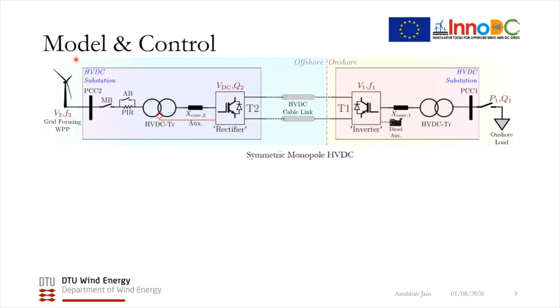The offshore wind power plant operates in grid forming mode, which means it controls the voltage and frequency of the offshore collector grid. Thus, the offshore MMC controls the voltage of the HVDC export link. The onshore MMC then controls the voltage and frequency of the onshore PCC because there is no grid available. Instead, we have a block load which is energized to demonstrate the black start capability of the HVDC connected offshore wind power plant.